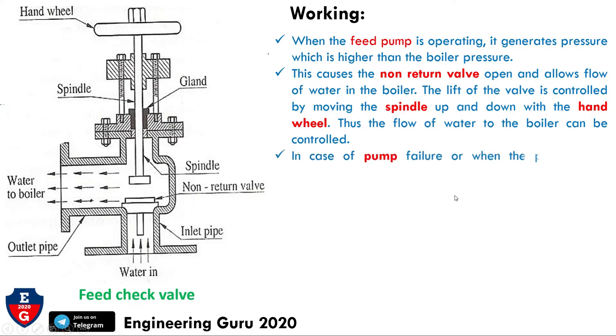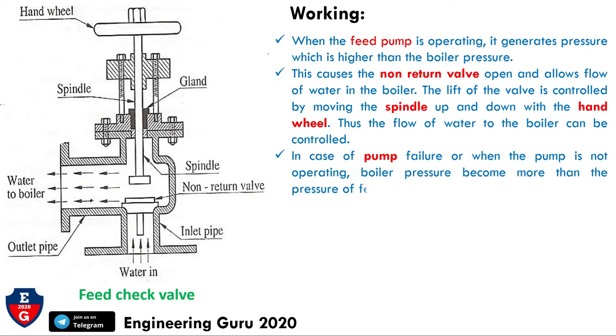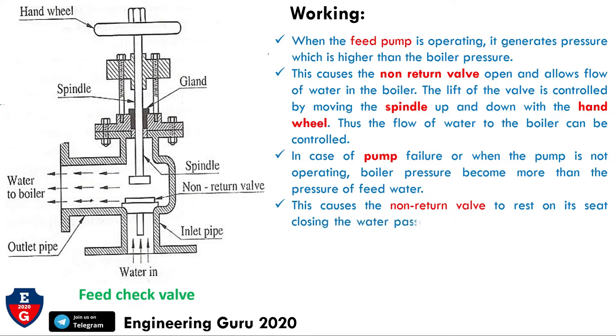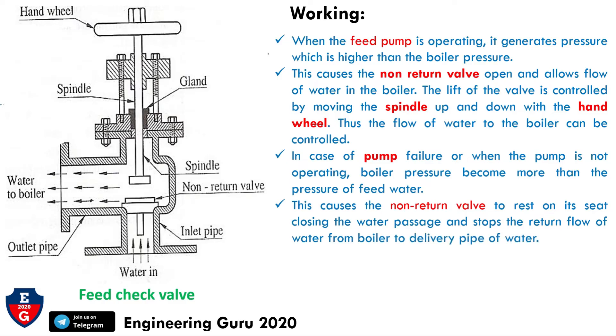In case of pump failure, or when the pump is not operating, the boiler pressure becomes greater than the feed water pressure. This causes the non-return valve to rest on its seat, closing the water passage and stopping the reverse flow of water from the boiler to the delivery pipe.